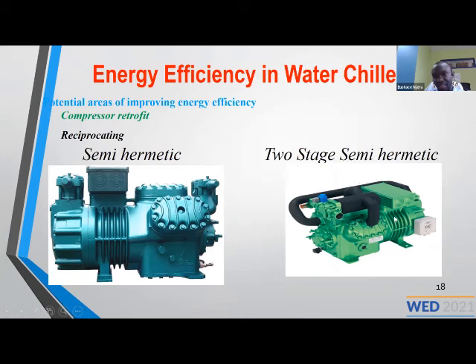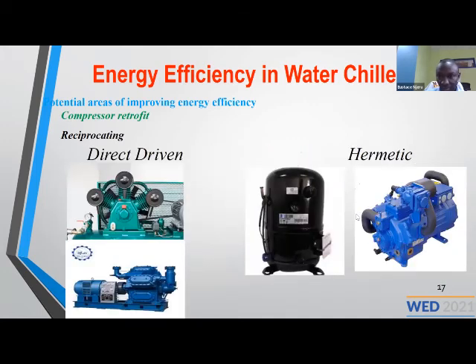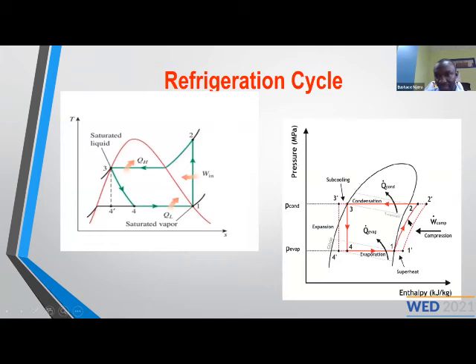There's a two-stage semi-hermetic, the one in green. The difference between semi-hermetic and hermetic is that the motor is not enclosed in the same place as the compressor, so you can service them. In this case, motors are serviceable. This one is two-stage to be able to increase the pressure. For you to do the cooling better, sometimes you require higher pressure. As you have seen in the TS diagram, for you to release a lot of heat in the condenser, you need higher pressures.